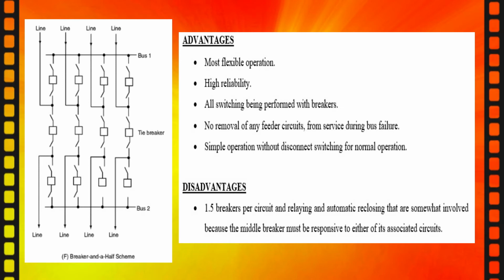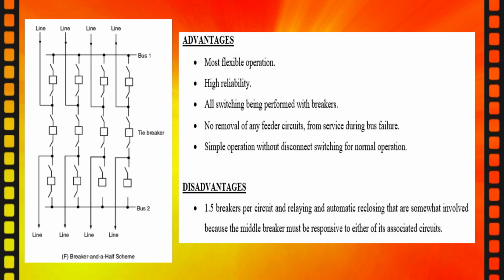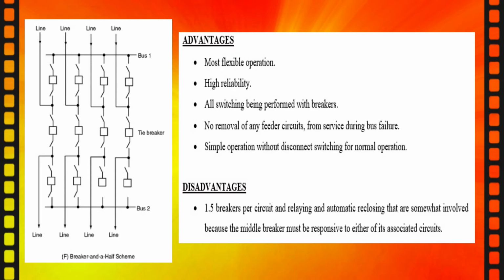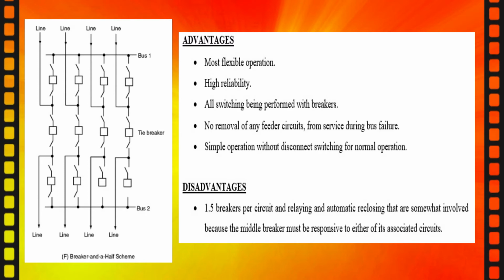Okay, for this, the disadvantage is 1.5 breakers per circuit, and relaying and automatic reclosing are somewhat involved because the middle breaker must be responsive to either of its associated circuits. This is the disadvantage of this breaker and a half diagram.